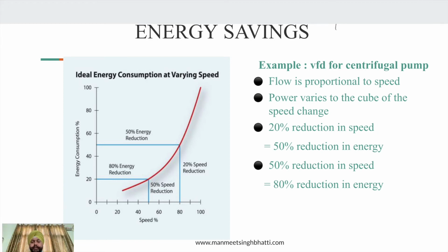In the same way, you also have energy losses, because all the motors are running at your maximum speed. So you are not reducing any speed, you are not controlling any kind of frequency. So if a motor has, say, 10 ampere current load, it will continue to have 10 ampere current load irrespective of whether you are crossing the pressure threshold required at the end.